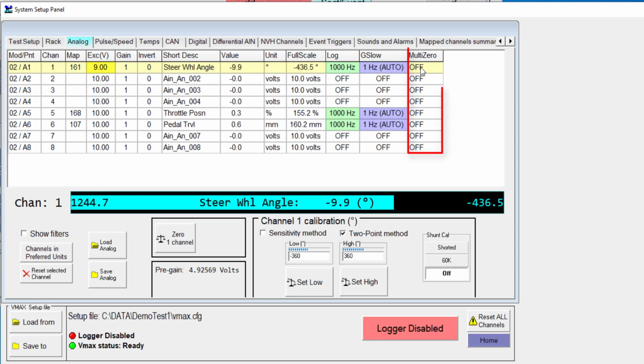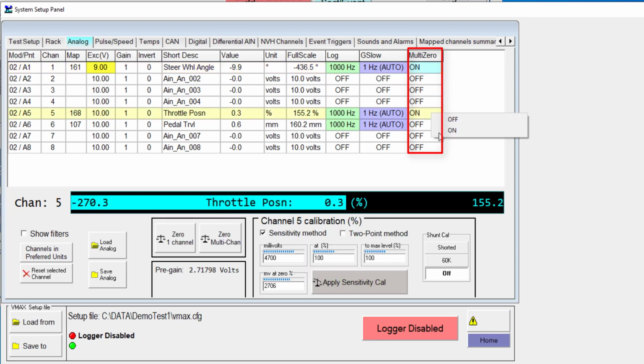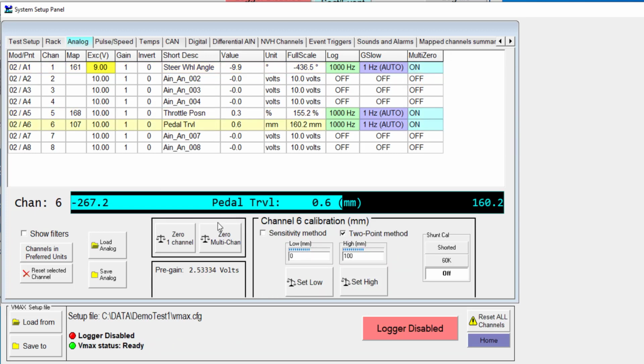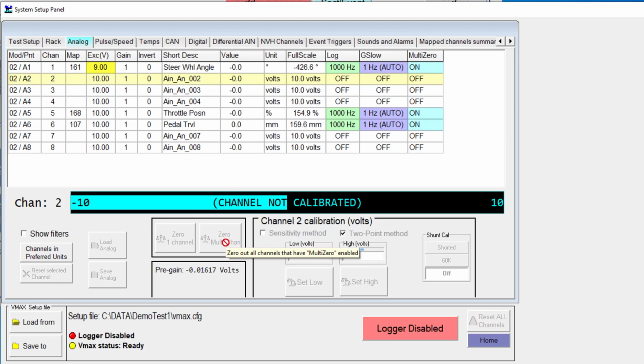We have this multi-zero field, and if you turn this on, you're going to notice that you get this 0 multi-channel button. Anywhere I'm in this table here, if I hit this 0 multi-channel button, we should see all 3 of these channels get zeroed at the same time. Okay, so you can see that that's happened. While I only have 3 sensors right now, that might not be super important. You might get to where you have a couple hundred analog inputs that all need to be zeroed simultaneously before you start collecting your events. That could be very important.